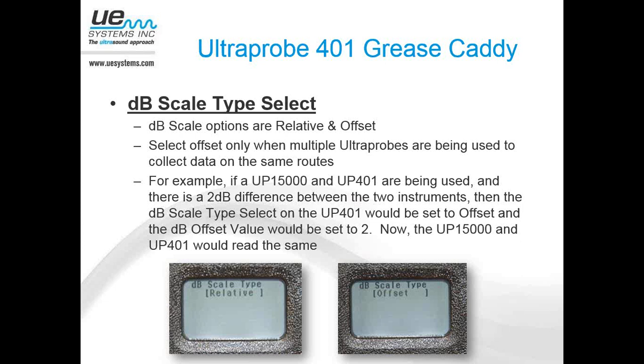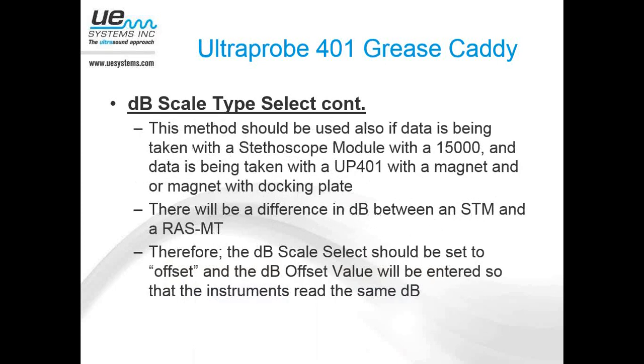And that way now your Ultraprobe 15,000 and your 401 are going to read the same. Now another scenario is going to be if you're using any other instruments, say a 9, a 10, or a 15, and let's say you're using the stethoscope module to collect the data, and then you've got the magnet with the 401. You will get different decibel level readings between the stethoscope module and the magnet. The stethoscope module tends to be a little more sensitive than the magnet.